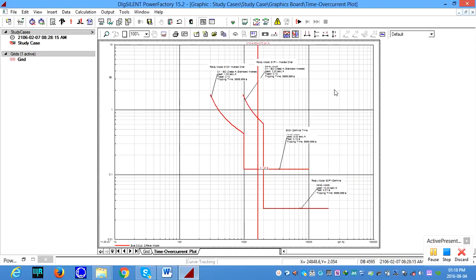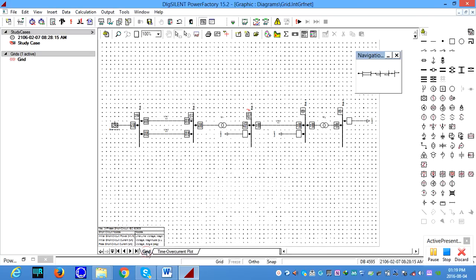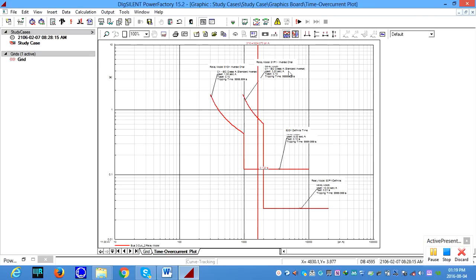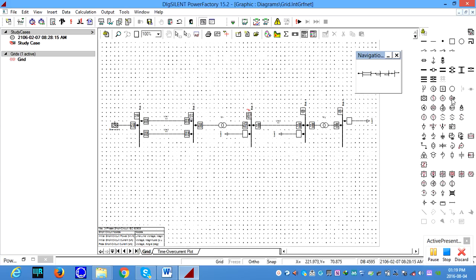Okay, it means you can see the relay is tripping. The relay is tripping at 0.12 seconds and the fault current value is 1634 amperes. We apply different types of faults to validate, and you can also see here the tripping time of the relay as well.